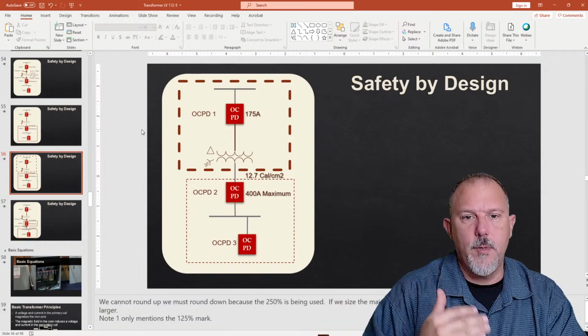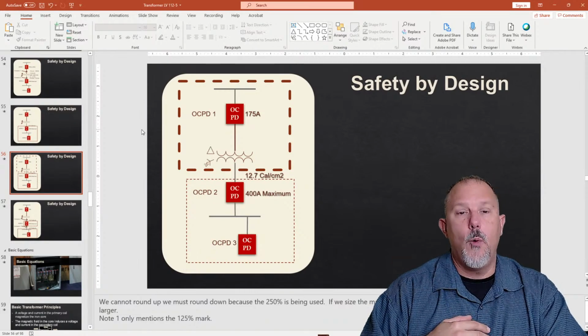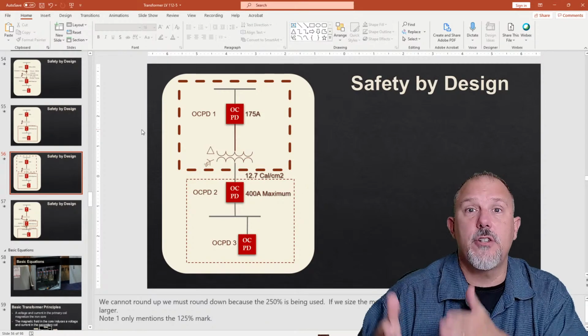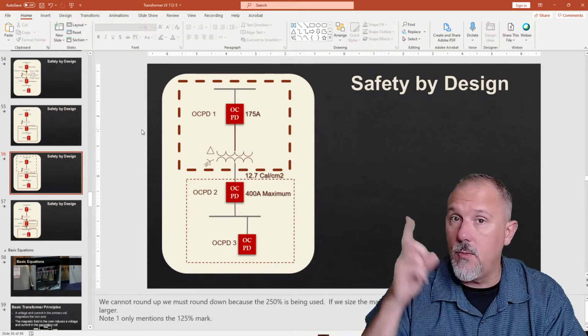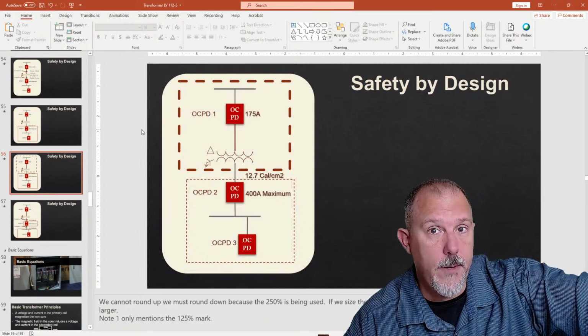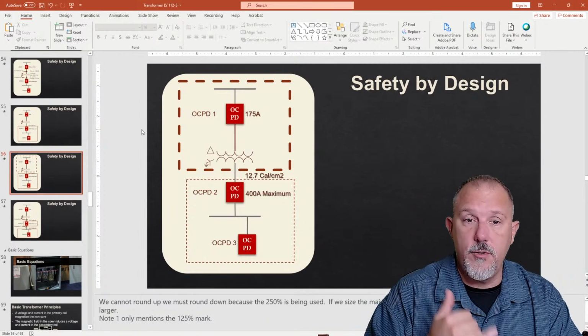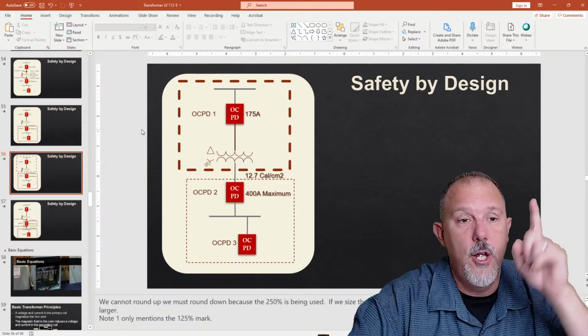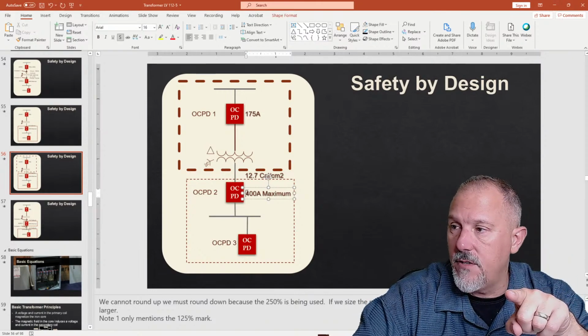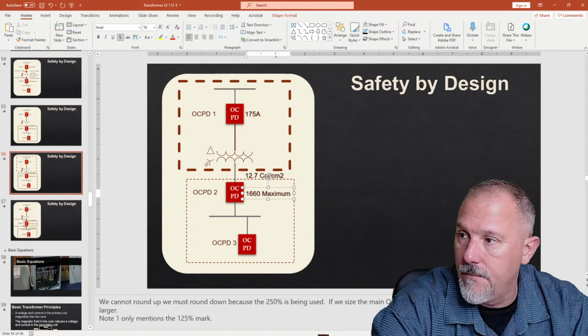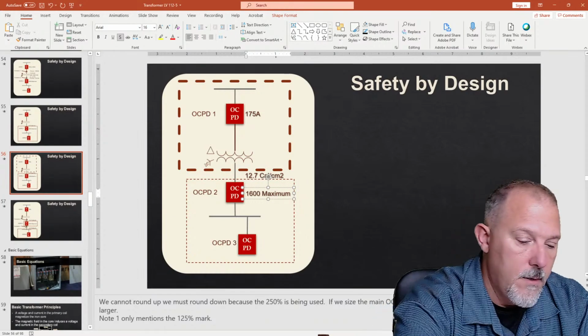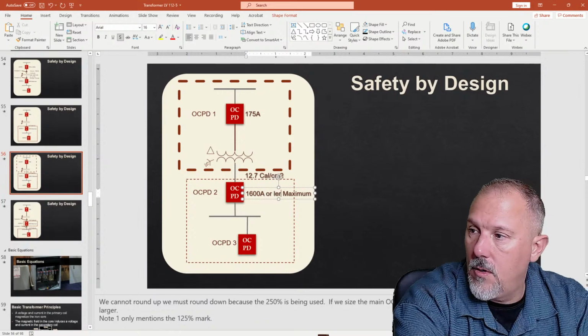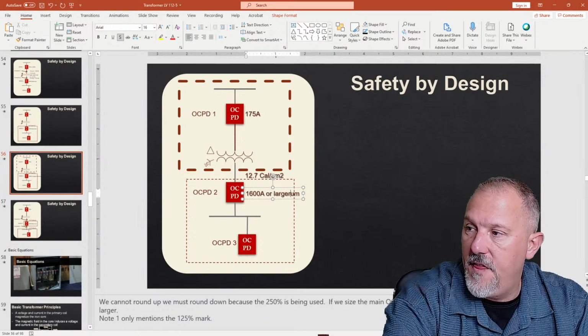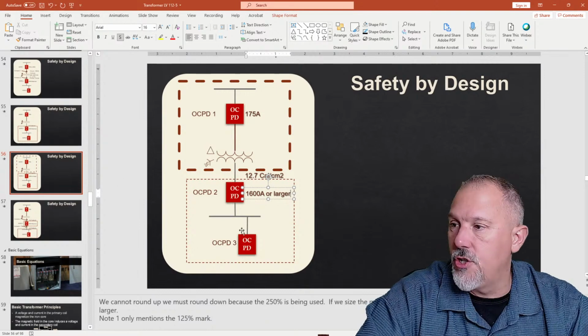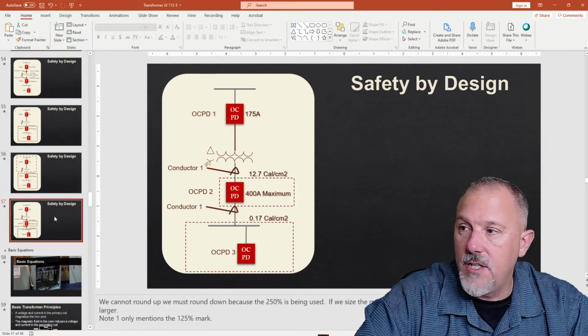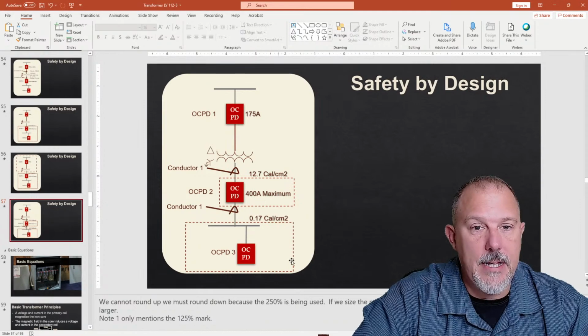And now I have 12.7 calories. And what do I do about it? So how do I establish an electrically safe work condition? I've got to call the utility. I'm not going up on the pole. I'm not pulling my meter, right? I'm not going to do any of that. I'm going to have to call the utility to establish an electrically safe work condition. So what this code says is if this overcurrent device here is 1,600 amps or higher, or larger, then I need to put it in its own enclosure outside of where these feeders are. So this is what it's doing. It's mandating this right here.